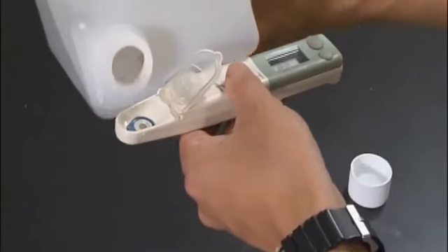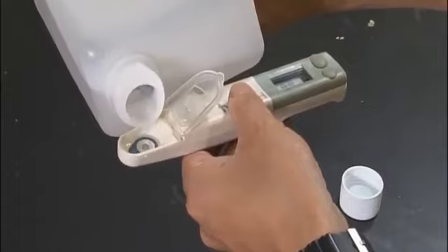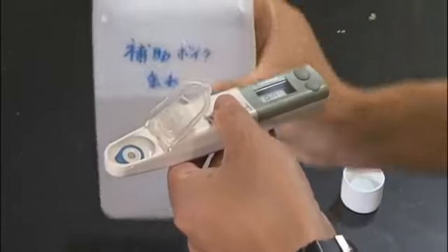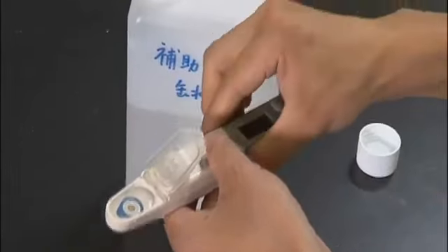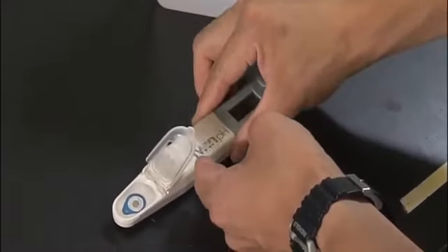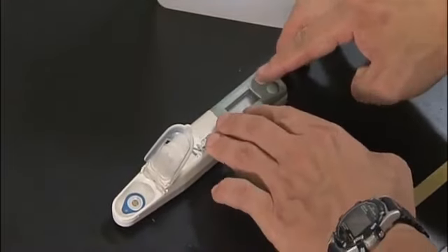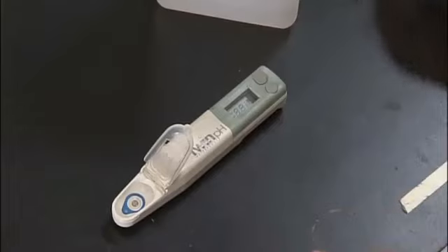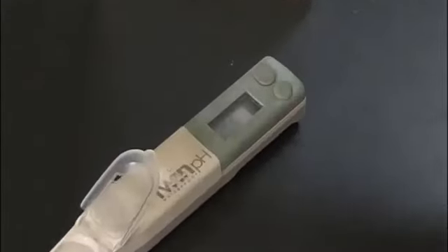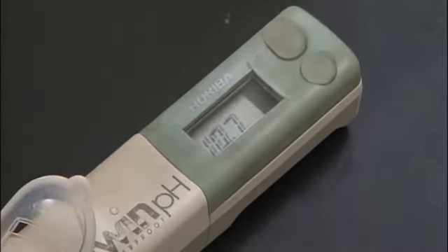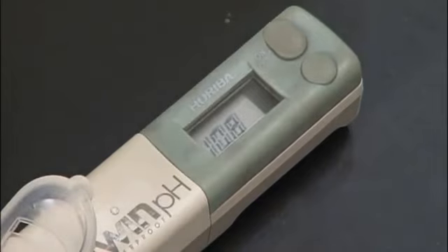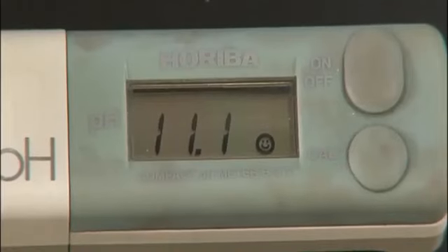You can also measure pH using a pH meter, although these are not included in the analysis kit. The pH meter allows you to accurately measure pH value. However, you must take special care when using the pH meter. For example, you must correct the pH meter using a standard solution. You must also remember to correct for the electrode's temperature.